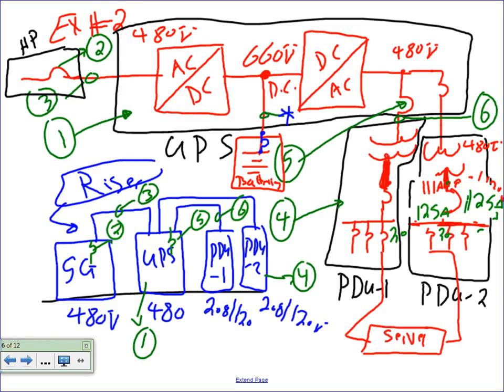Yes. And then, does the server know which power it's getting? The server doesn't care and doesn't know. Say this server was 10 amps: 5 amps will come from here, and 5 amps will come from here. That's all the server cares about. The server is DC. It takes the power at the AC level, and deep inside there is a conversion, another transformer, a little more conversion, and then right in here it's at DC level. So they have 2 sources at the DC level that they dump into the server. The 2 are connected to the server at the DC level. It's like paralleling, so if one goes down...